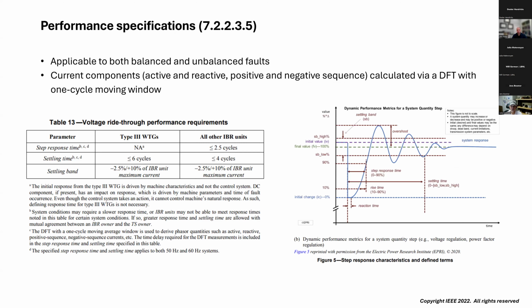Okay, so we know the type of current. We know that the magnitude of current may be specific to a given interconnection. So the next part of the standard talks about the time domain response requirements of those current components. Those are summarized in Table 13. There's a separate column for Type 3 wind turbine generators versus full converters or all other IBR units.